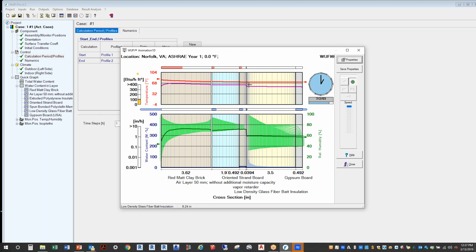And whenever your red line and your purple line cross, that's where you're hitting condensate as well. That's the dew point. The purple line's the dew point, boom, right there. You see the water shot up right here. Okay? So I'm going to close this. Is that one of those convergence points earlier in summer? Yeah. That's the dew point.